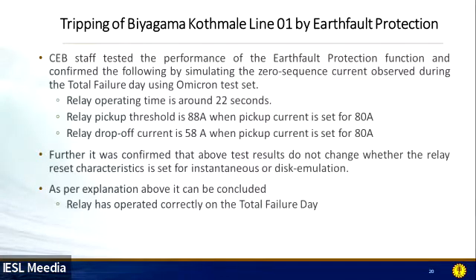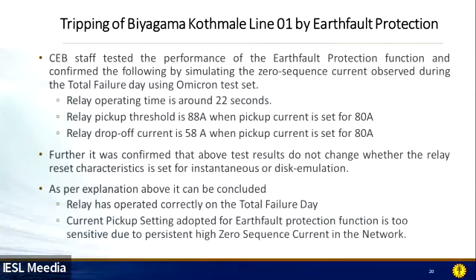As per the explanation above, it can be concluded that the relay operated correctly on the total failure day. The current pickup setting adopted for the earth fault protection function is too sensitive due to the persistent high zero sequence current in the network. That's the main conclusion we derived from the tripping of this line: we can't work with this 80 ampere current pickup setting.